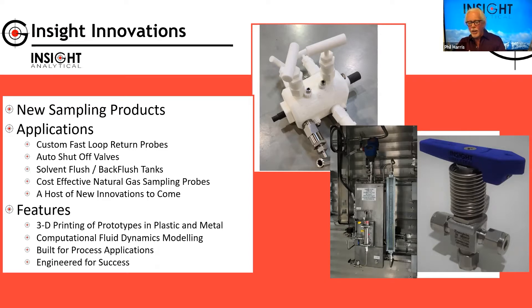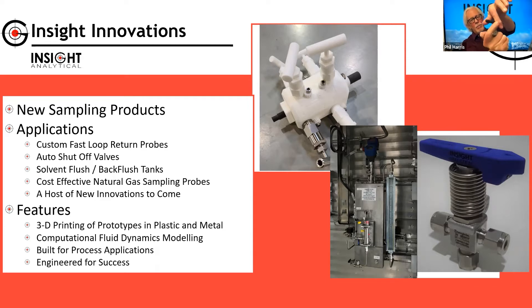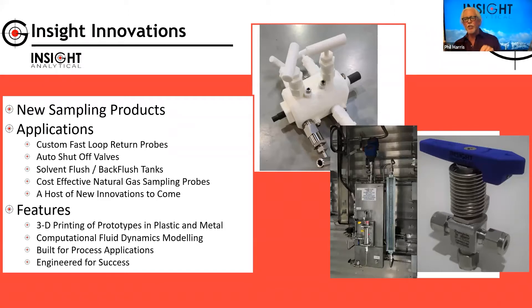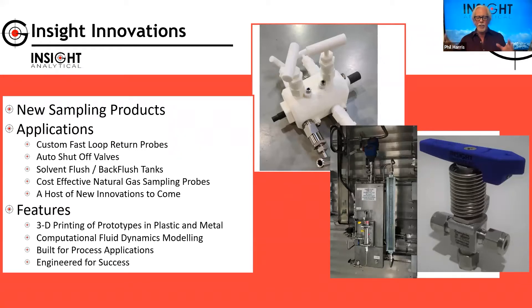On the bottom right you can see a valve with a spring on it — just like this one. What it becomes is an automated return valve. You turn it when you want to vent, hold it open, let it go, and it shuts off automatically. We'll do those on two-way and three-way valves and put these all through sample systems so that if we want a valve to be in a specific position most of the time, it can only be actuated when someone is holding it.